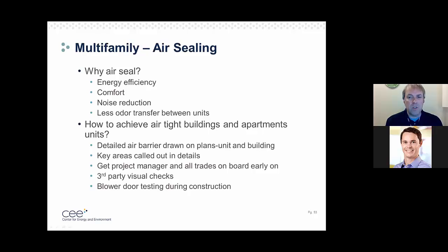Talking to builders, odor and noise transfer definitely leads to a lot of their callbacks down the road. Once we've worked with builders on tightening up common walls and corridor walls, they're definitely getting fewer complaints — they really understand and try to achieve that, since it seems to be quite a few of their complaints after the build is complete. To achieve airtight buildings, apartments, and units, we recommend a detailed air barrier drawn on the plans for the unit and the building, so each unit should have its own outline of where that air barrier is going to be.